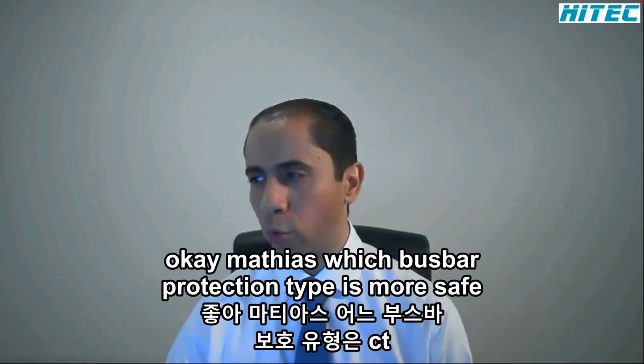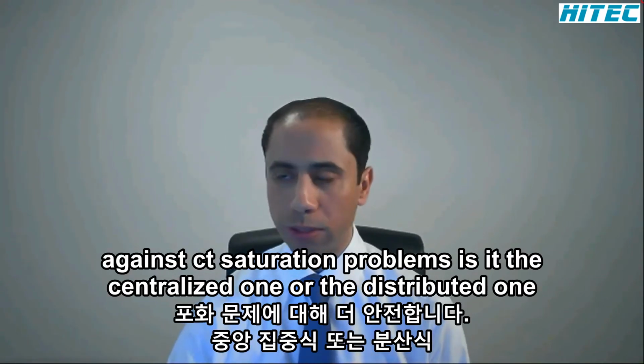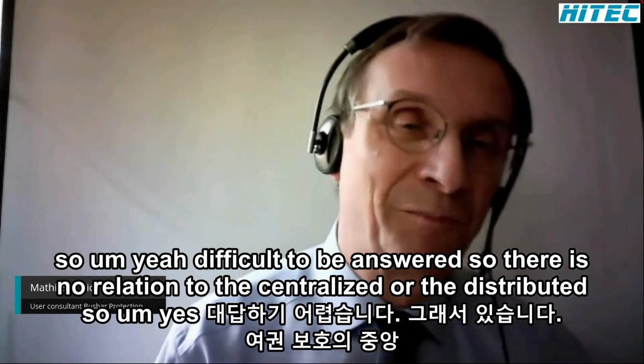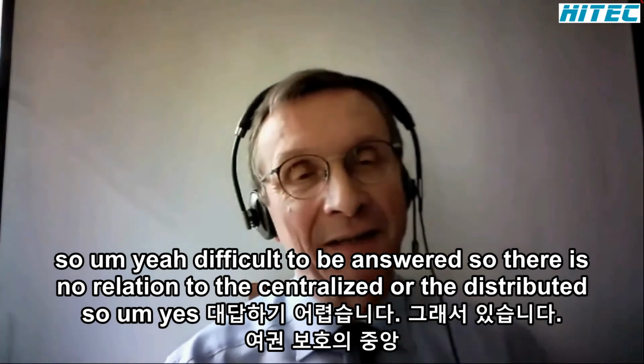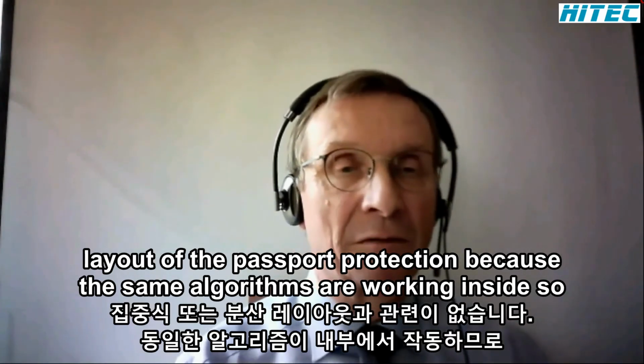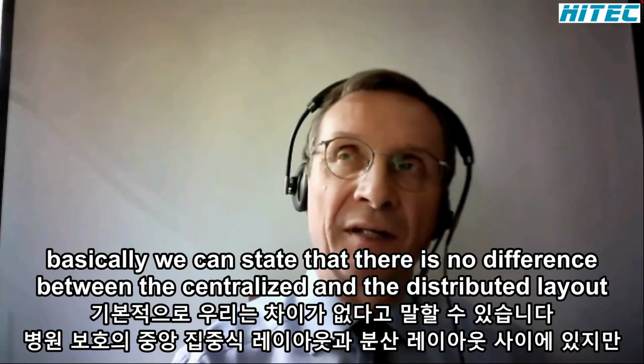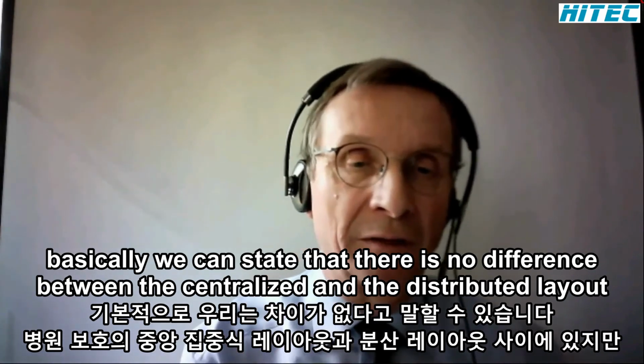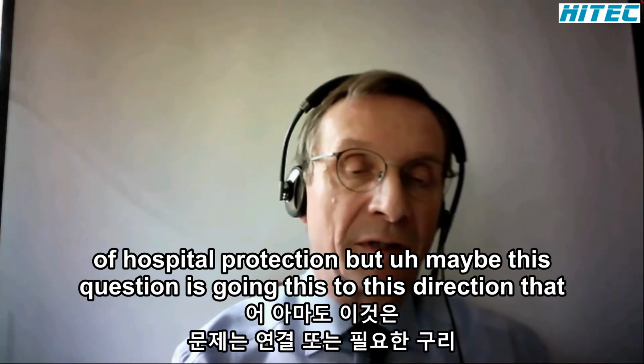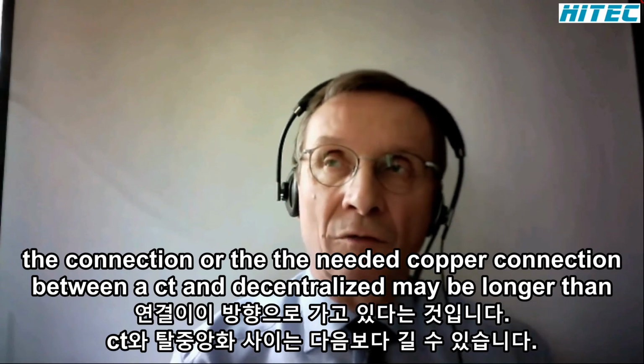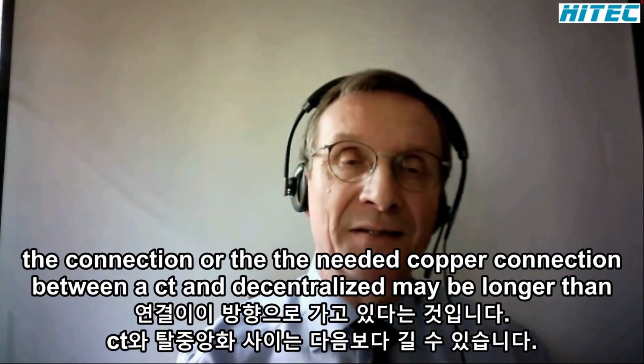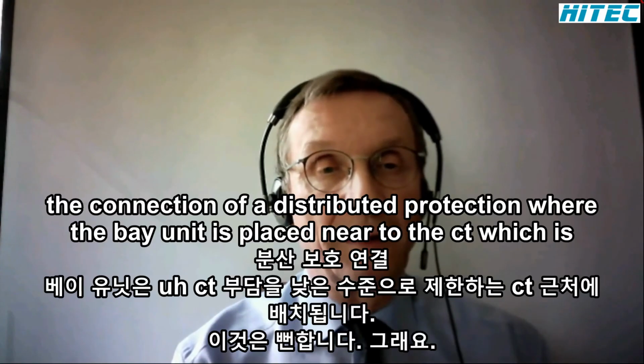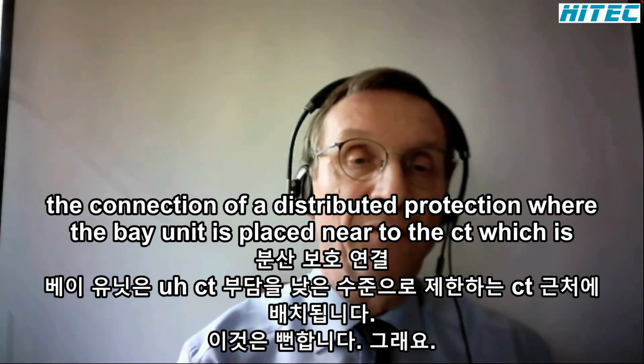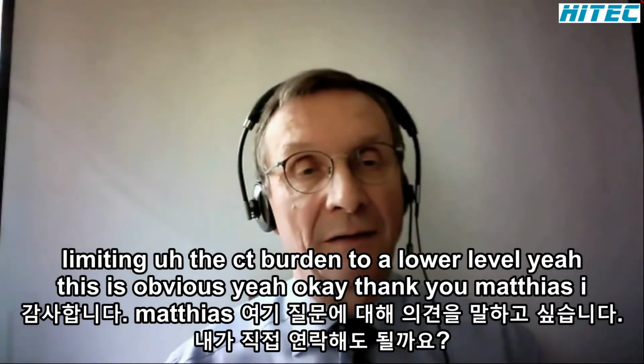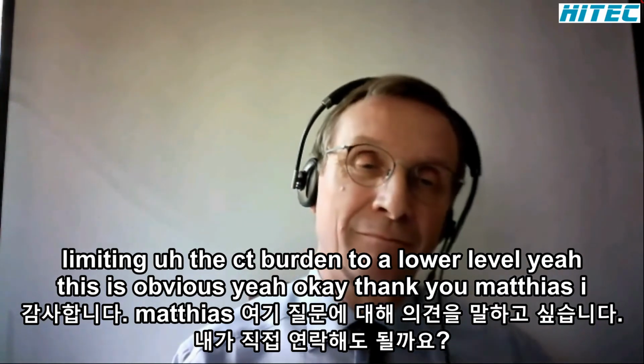Okay, Matthias, which busbar protection type is safer against CT saturation problems? Is it the centralized one or the distributed one? So, yeah, difficult to answer. There is no relation to the centralized or the distributed layout of the busbar protection, because the same algorithms are working inside. So basically we can state that there is no difference between the centralized and the distributed layout of busbar protection. But maybe this question is going in the direction that the needed copper connection between a CT and the centralized unit may be longer than the connection of a distributed protection, where the bay unit is placed near the CT, which limits the CT burden to a lower level. Yeah, this is obvious.